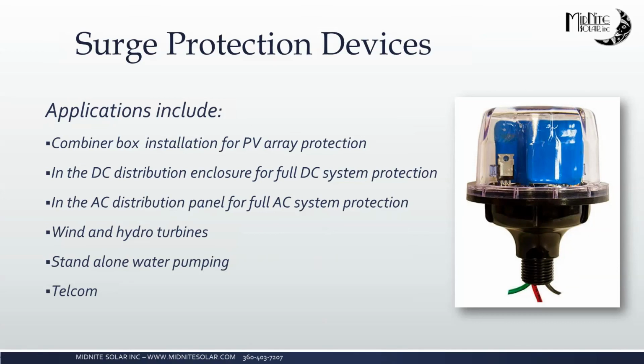These have a lot of applications, as I said. You can put them in your combiner box for your PV array protection, the DC distribution enclosure for your DC system protection, the AC distribution panel. So, for example, if you have an inverter, you would want to put an SPD on the AC out of that inverter so that anything that came in from the house electrical would be stopped before it came back and damaged that inverter. It's great for wind and hydro systems, especially wind.